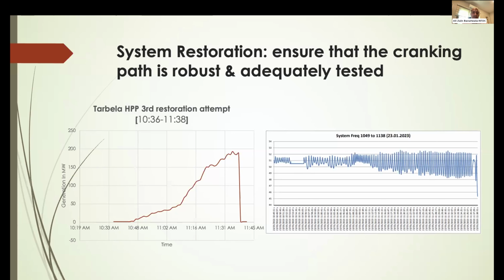So every time we tried to put load on these governors, you would see the frequency spiral out of control. On the left, you see for example the third restoration attempt at 10:30, with 2 units. You start the first unit, the red line, you start putting some load, connect some 11 kV feeders in the nearby distribution company, and you have fairly close control of the system frequency for this island. Then after a while the line jumps up a little - that's where you add a second unit.